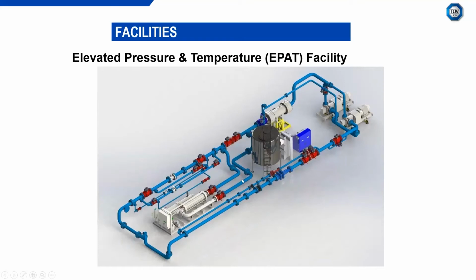There's a bypass system that takes it through a compact prover. That's the Emerson Daniel 60 litre compact prover. We have the S600 plus flow computer that works alongside that for pulse interpolation of our turbine meters. As you can see, the outlet goes through various manifolds. We've got 3 banks of turbine meters. These are Faure Herman helical blade turbines, ranging from 1.5 inch, 3 inch, and 6 inch in diameter. It flows back round into the test section. We've got 2 main test sections. We have a 6 inch line, the main line, and then we have a bypass 3 inch line. We have double block and bleed valves so that we can direct through either or, and then it flows back round again. This here is our pressurization unit, so that controls the pressure in the line.